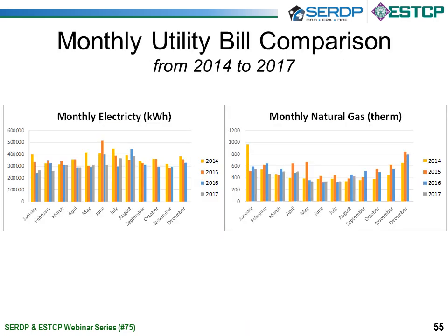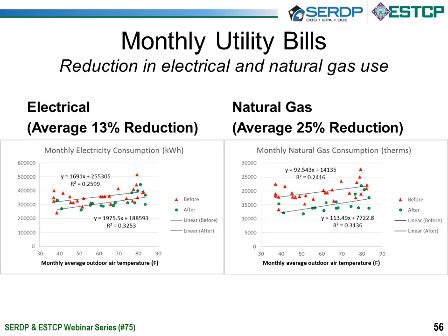I want to now turn to savings for the building overall. This data represents monthly data from 2014 through the middle of 2017. It's kind of difficult to see the savings on this, so I'm going to move on to the next plot where we plot the same data on a monthly basis. We have electricity on the left, natural gas on the right figure. Each point represents a month. Red are for months before. Green represents months after. And to estimate the average difference, that is improvement associated with correcting faults identified using this technology, we regress on the two sets of points and determine the average difference between the two lines. We found an average electricity consumption reduction of 13% for this building and a 25% reduction for the natural gas consumption for this building.